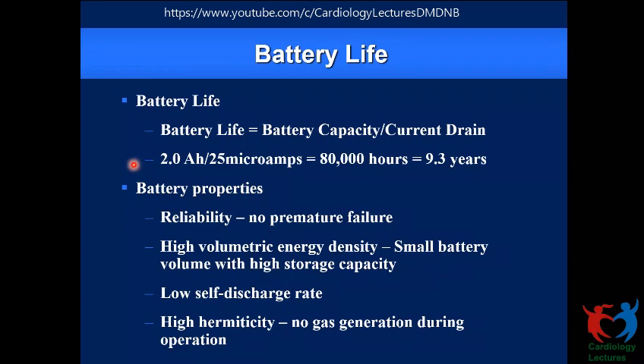So there is a certain amount of baseline current consumption and also additional current consumption because of these additional activities by running the algorithms, etc. So we will not be able to calculate what is the continuous current outgo. The pacing output current drain is one of the aspects of this. So in this case, if we can calculate the continuous current outgo for this 2 ampere hour battery, in this case, let's say 25 microamperes.